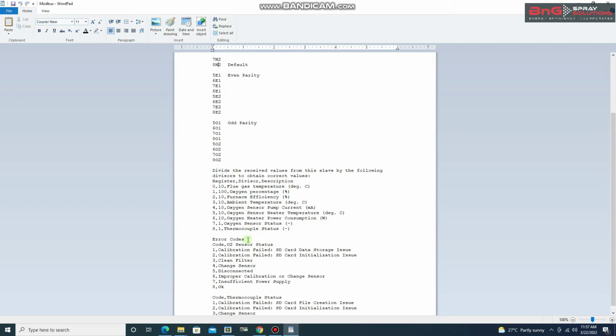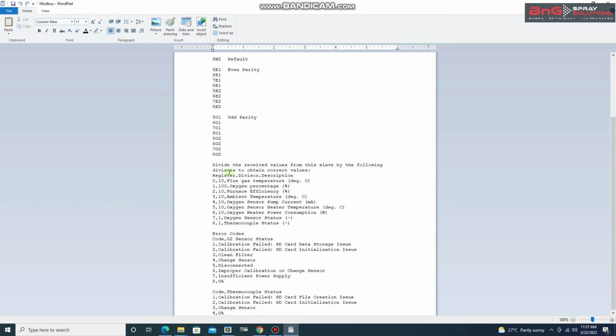One more thing that you need to take into account is that the data that is received by the master, which can be a PLC or a computer, will all be received as 16-bit integers. Now, the oxygen percentage ideally should have 2 significant digits after the decimal point. So it will come as a multiple of 100. So when you receive the data, you need to divide the received values by these divisors. So for example, flue gas temperature should be divided by 10, oxygen percentage value, whatever you receive at the PLC, should be divided by 100, and so on.